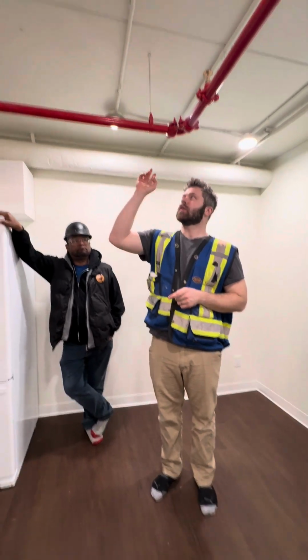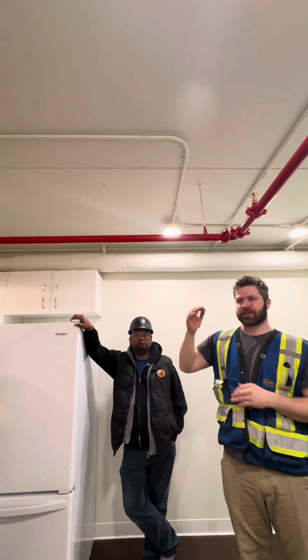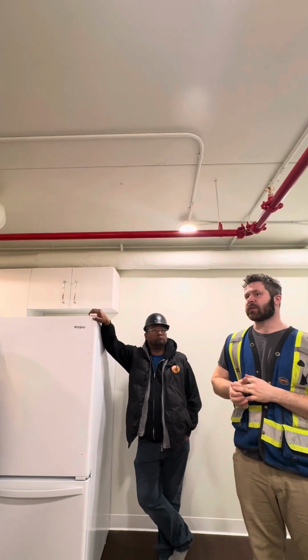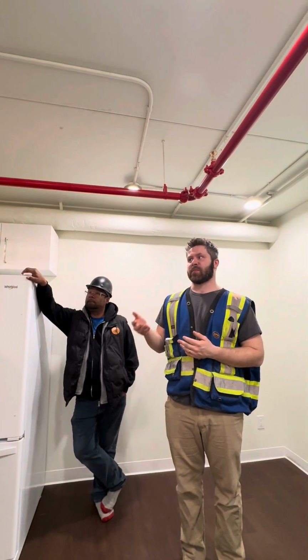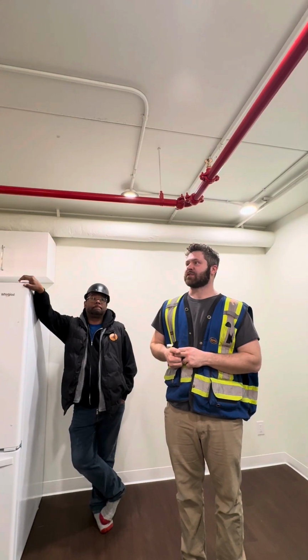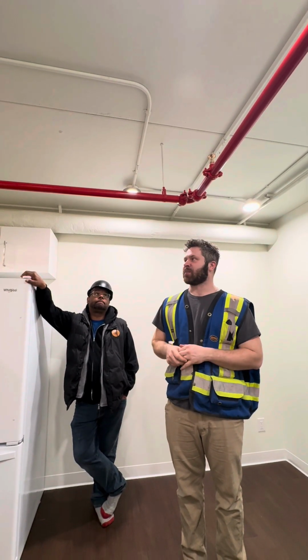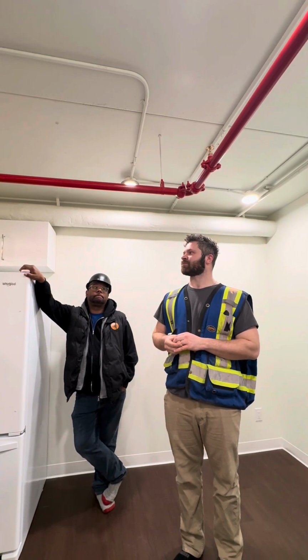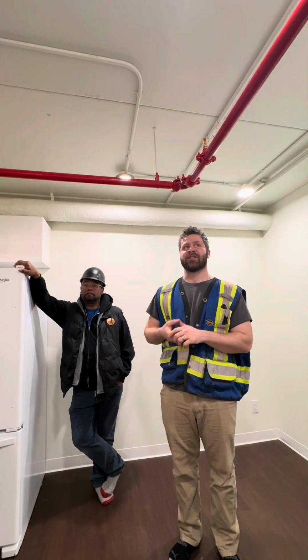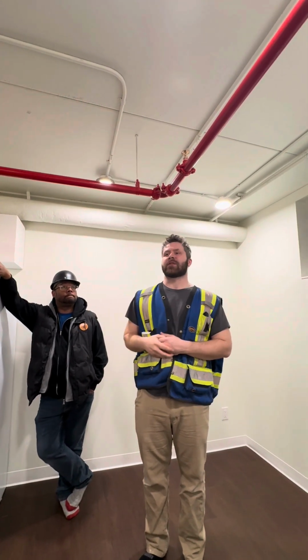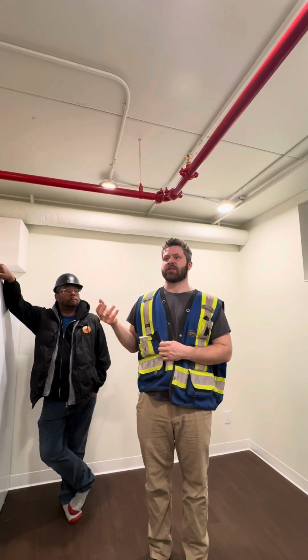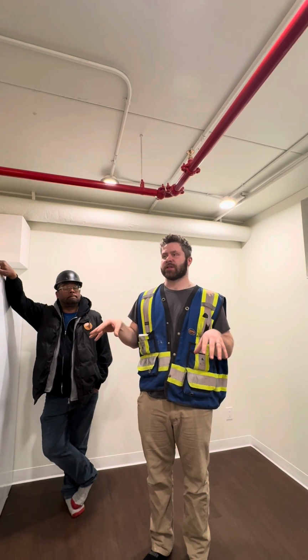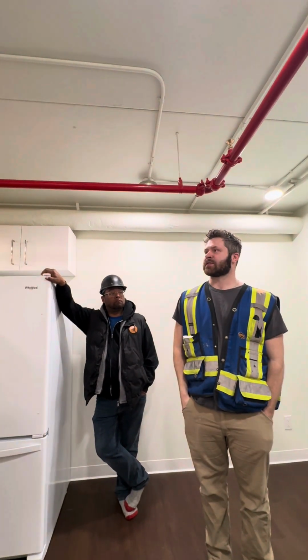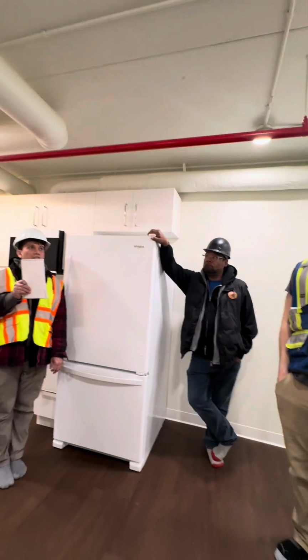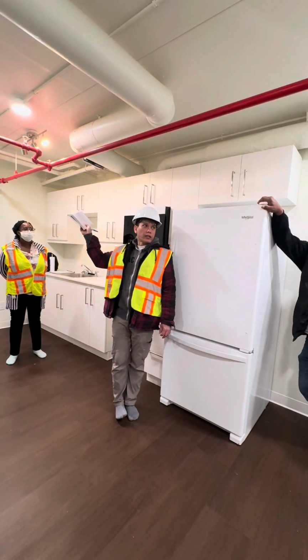As far as indoor units, we can go up and show you where these pipes are. Specifically in the basement, due to height restrictions that we don't have on other floors, they're particularly low in comparison to other floors. They are of a code-compliant height, but just from a maintenance standpoint, in conversation with your tenants, make sure you're really communicating with them not to touch them. They're painted red to clearly indicate what they are and their importance. Under no circumstance should they be touching them or hanging off them. If these pendants were to get hit and the glass bulb were to break, that would obviously cause an alarm in the building. So just wanted to make note of that. On this floor, basement specifically, they're low. So that'll need to be communicated with your tenants. The emergency shutdown for this water line will be outside.